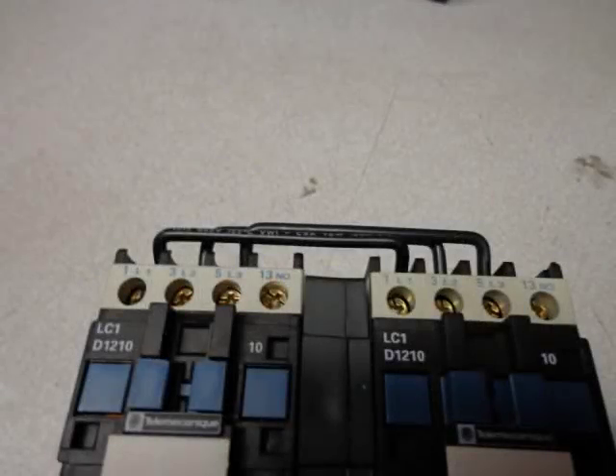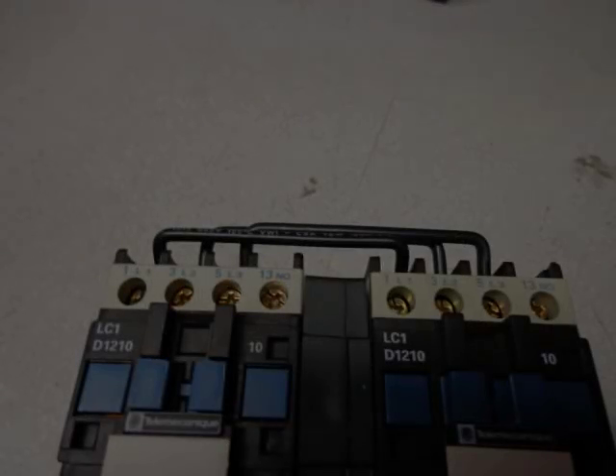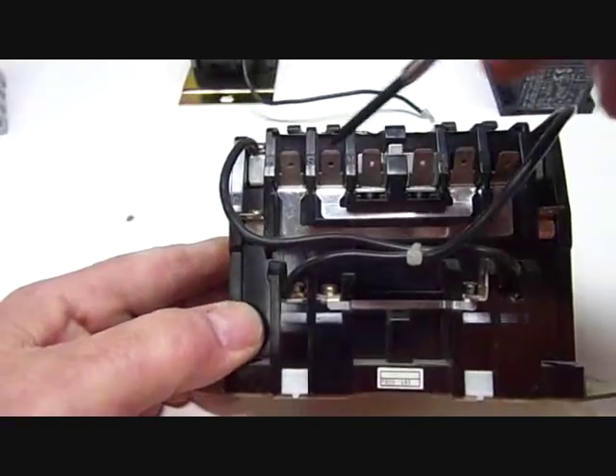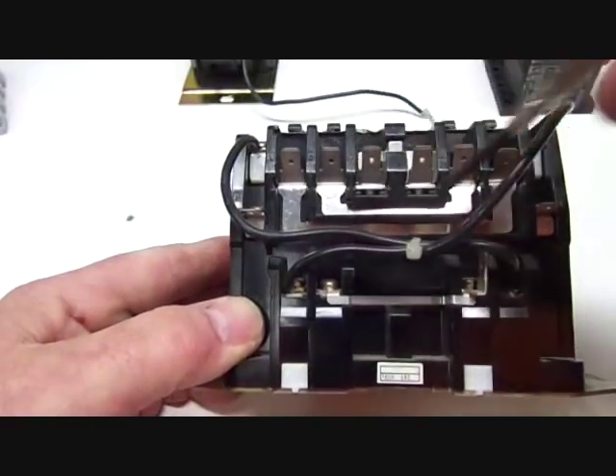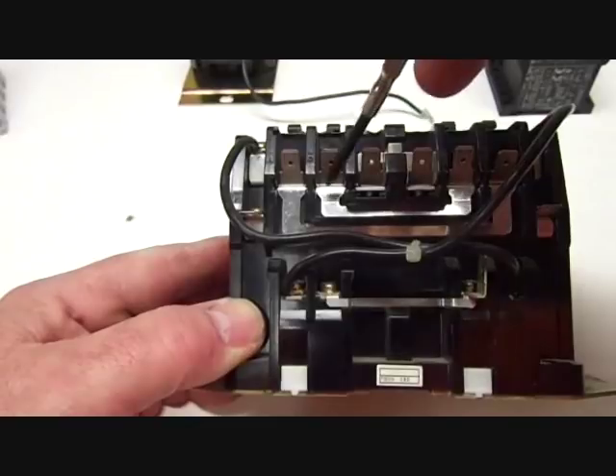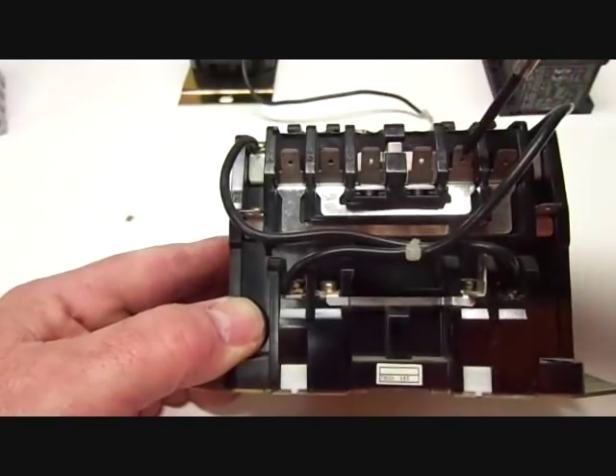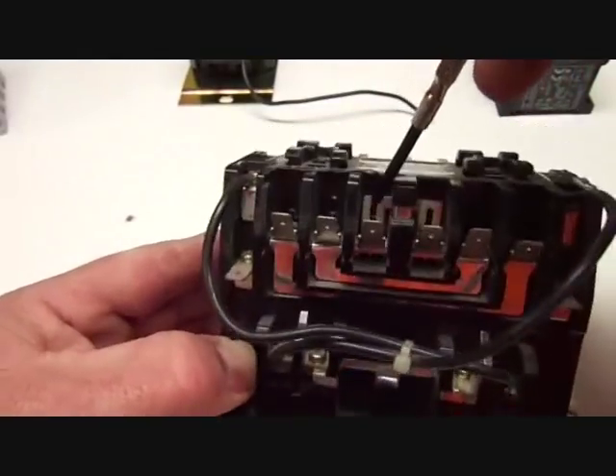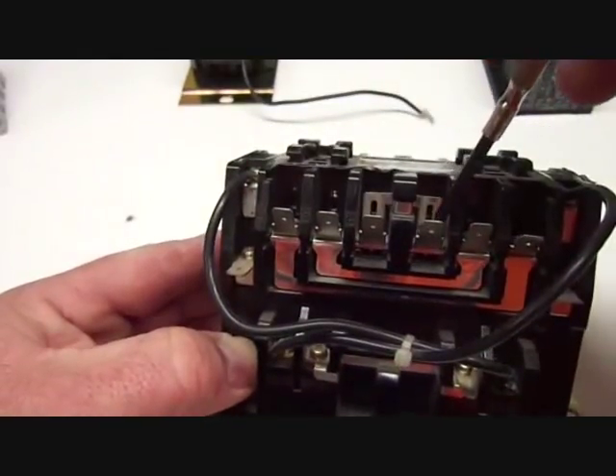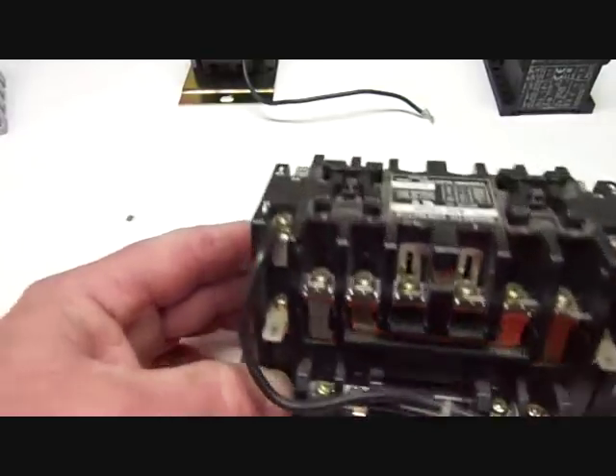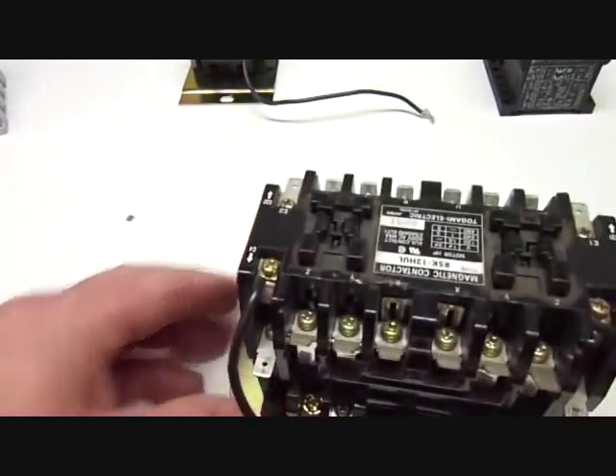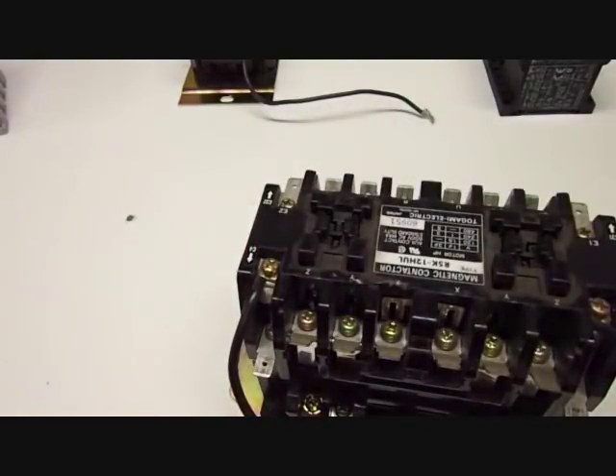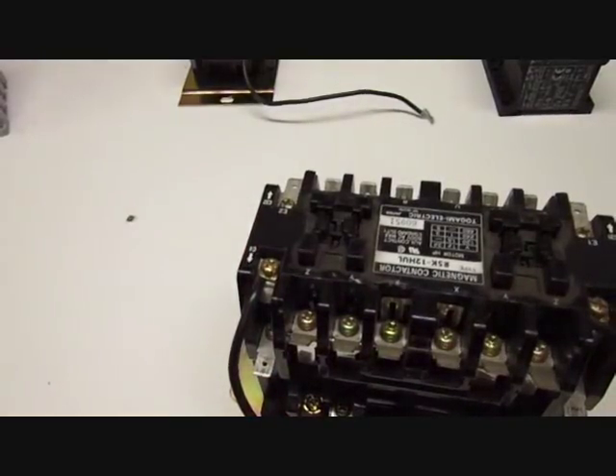Some of these reversing contactors come with jumpers built right into them from the factory, and it's going to have two of the poles already swapped on one of the contactors. That phase swapping can happen on the load side or the line side, it doesn't matter, and usually they make it so you can remove those jumpers if you need to.